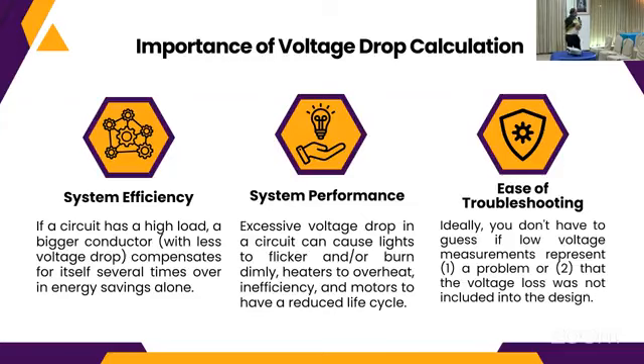So, we have a lot of experience of this in our project. No? Because of the distance, malayo siya, so we need to upsize the size of the conductor from, halimbawa, 100 mm squared to 125 mm squared. So you need to compute. So there are some percentages that our voltage drop calculation should pass. So I'll show you later.